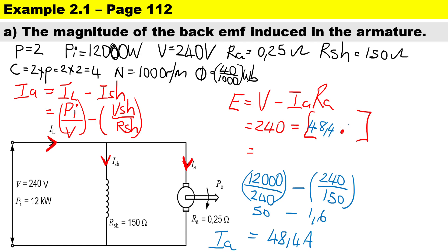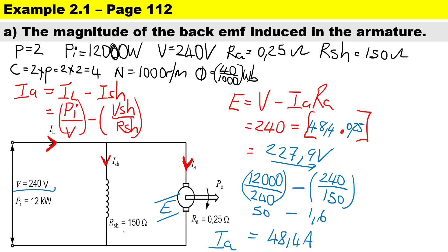Substituting I_a = 48.4 amps and R_a = 0.25 ohms into E = V − I_a × R_a gives us a generated EMF of 227.9 volts. Notice that for a motor the EMF is smaller than the terminal voltage. The EMF is generated by the armature assembly, while the terminal voltage ensures the machine can operate.